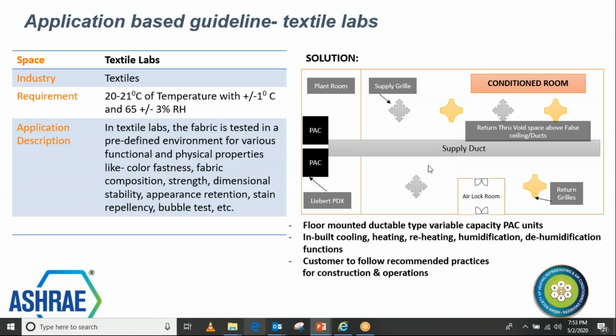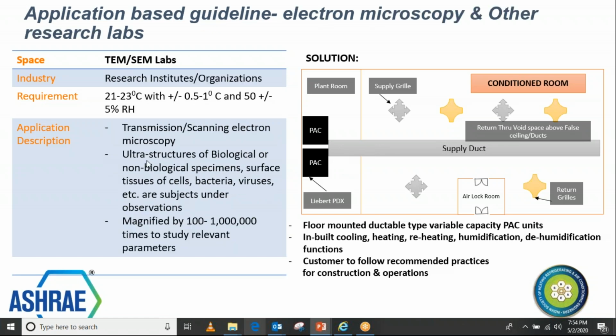So it is very important to have proper air circulation from the supply and return point of view. At the same time, if you are able to have better control on the compressor, on the fan, and on the heater, the reheating, especially here, there are different types of cooling units designed for this kind of application, because here the sensible load is not 100%, it is lower. So the cooling systems must be carefully designed with a built-in provision for reheating also, because the load is lower most of the time there.